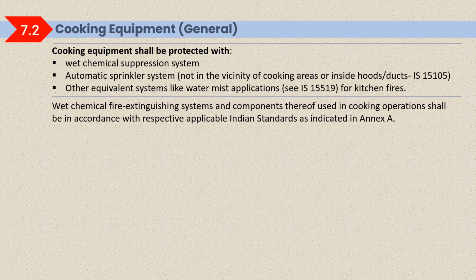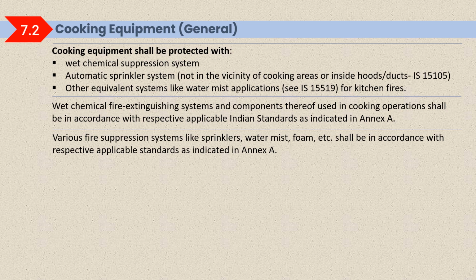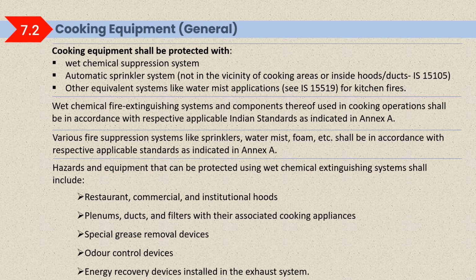Wet chemical fire extinguisher systems and components thereof used in cooking operations shall be in accordance with the respective applicable Indian Standard as indicated in Annexure A. In Annexure A, there is a list of relevant standards that are mentioned in this standard. Various fire suppression systems like sprinkler, water mist, foam, etc. shall be in accordance with the respective applicable standard as indicated in Annexure A. Hazards and equipment that can be protected using wet chemical extinguishing systems shall include restaurant, commercial and institutional hoods, plenums, ducts and filters with their associated cooking appliances, special grease removal devices, odor control devices, and energy recovery devices installed in the exhaust system.